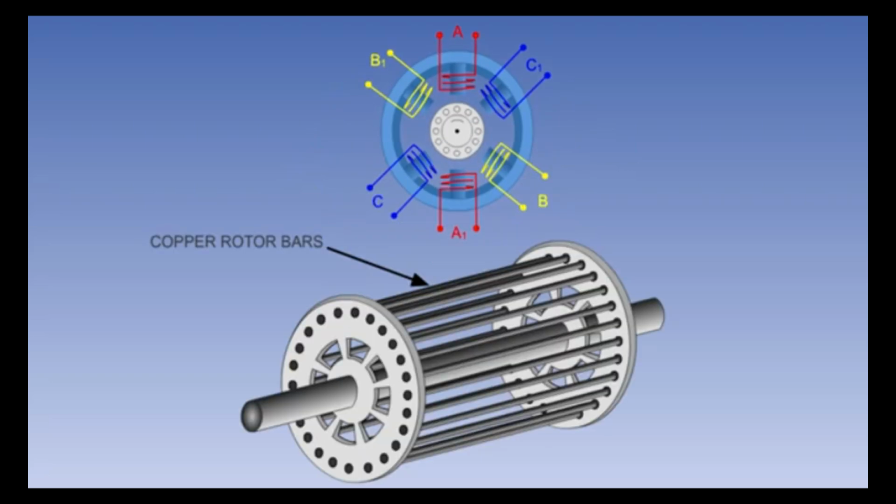The rotor usually consists of a cylindrical laminated iron core which has a number of longitudinal bars of copper evenly spaced around the circumference. These bars are joined at either end by rings of the same material to form a composite structure called, because of its shape, a squirrel cage. The rotor bars are made of very low resistance material, so that a large current can flow through them.